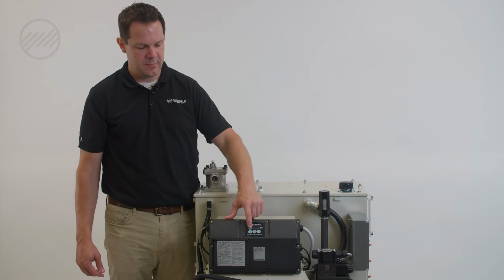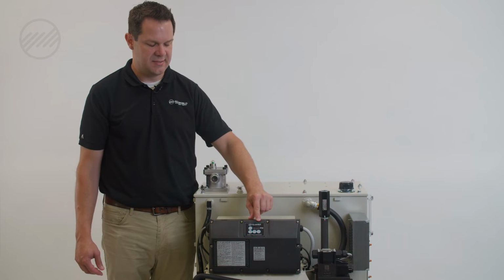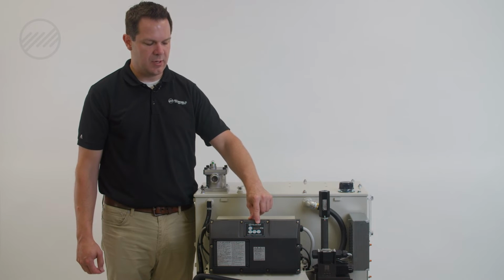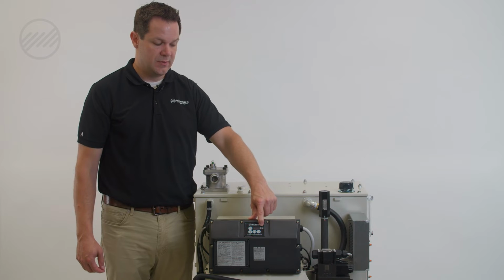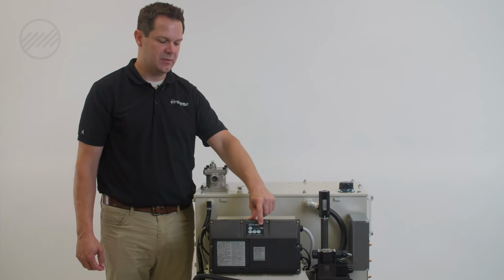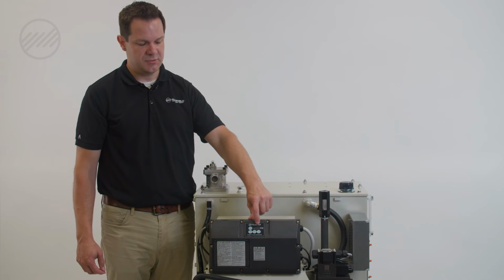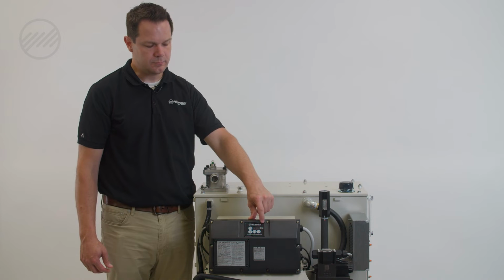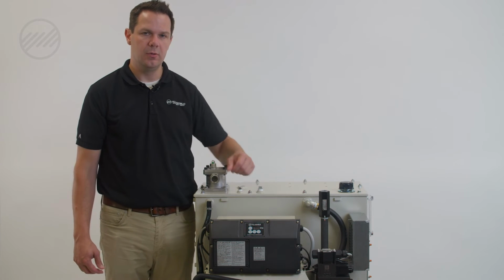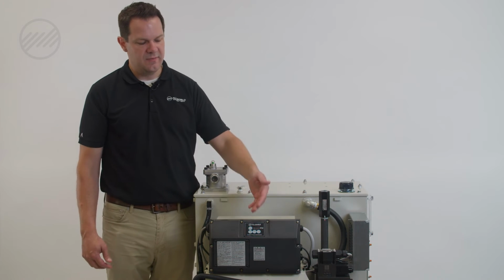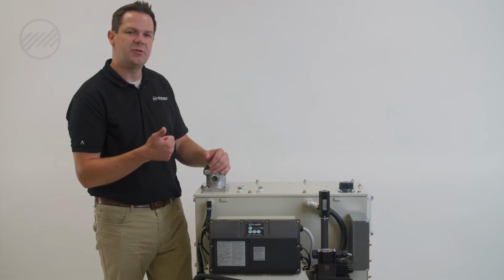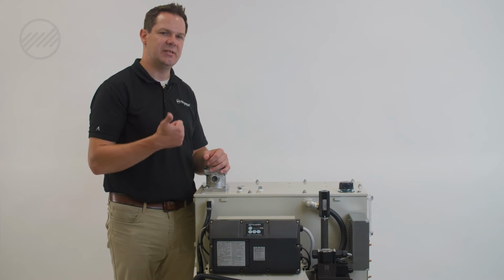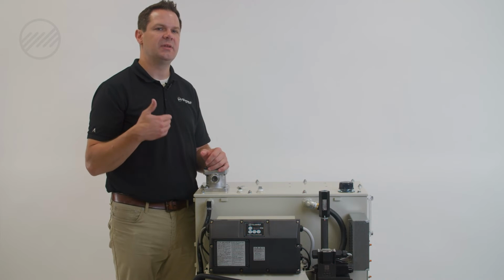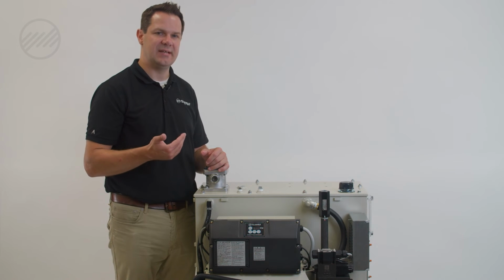We can check our RPM by hitting the menu key, up arrow to N05. This will display the motor RPM minus a 0 in the one spot. So if it shows 35, that's 350 RPM. If it shows 60, that's 600 RPM. Ideally, we want this to be below 35 or 350. If that number has exceeded that, we want to make sure nothing has changed in our circuit, such as a leaking actuator, a valve that's stuck, something that would create an open loop for oil to the tank. The unit will work hard enough to overcome that, and then ultimately generating heat.